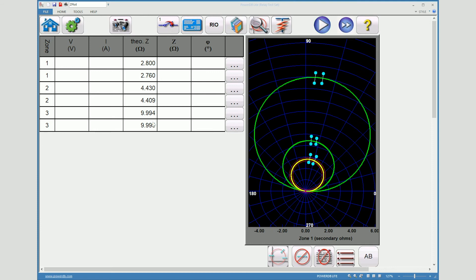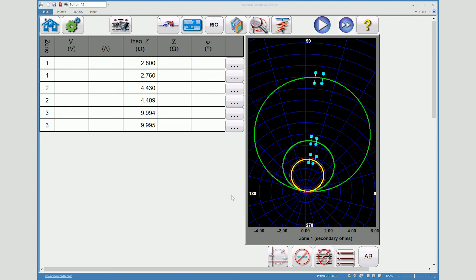And now what we'll do is we'll allow what type of fault that we would like to create. So we need to see what types of faults are available. Selecting the different fault type button allows us different fault types that we can select during this test. So we can actually choose a three phase fault, phase to phase fault, and then also phase to ground. Well, since I selected some points and I was already going to do my phase to phase values, I went ahead and selected the A to B. So you'll let it let you know here that we're on A to B fault.